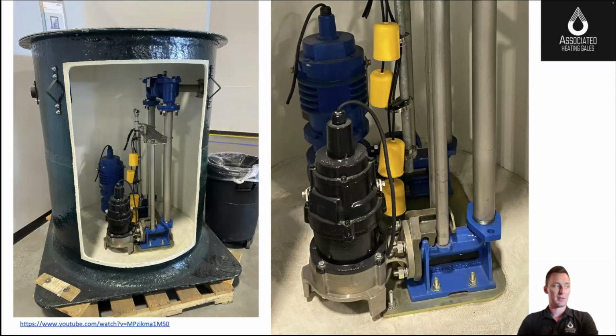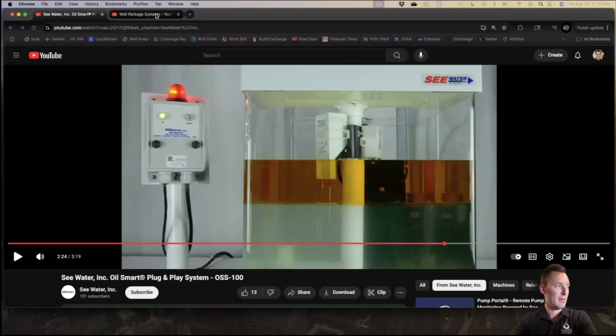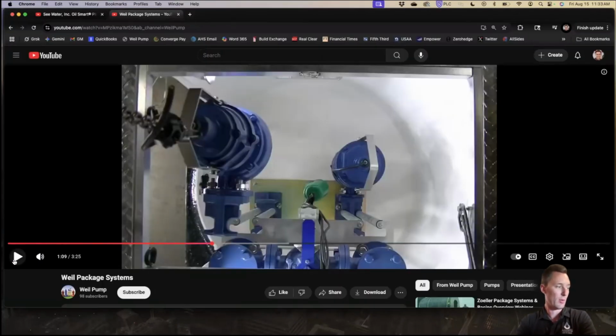This is also a must for a system where you see on the left here where you need a flush cover. So you're heading out the side of the basin with the discharge, the vent, the electrical, and you need a flush cover. Nothing's coming up through the cover. You're going to need a rail system. Otherwise, they have to undo quite a bit of plumbing just to get a pump out. So let's look at a video here of this rail system. It'll give you an even better look at how it works.